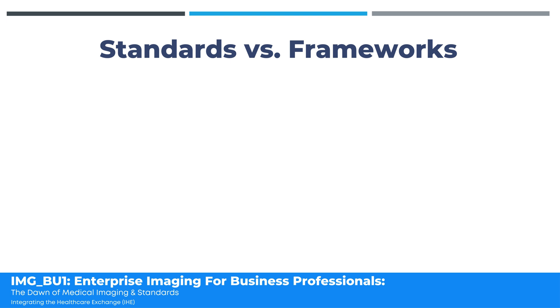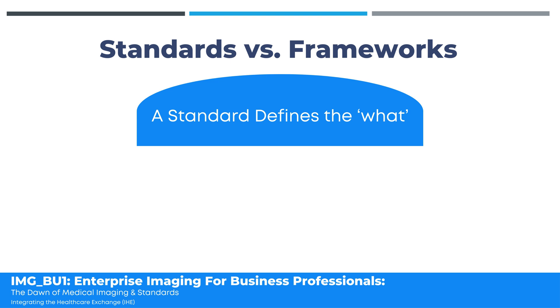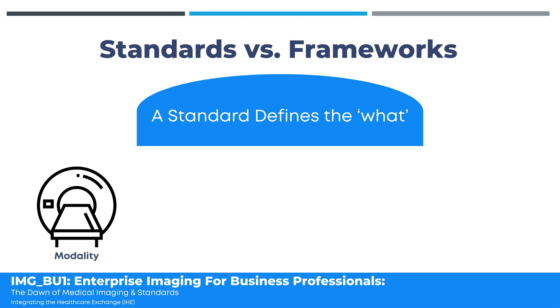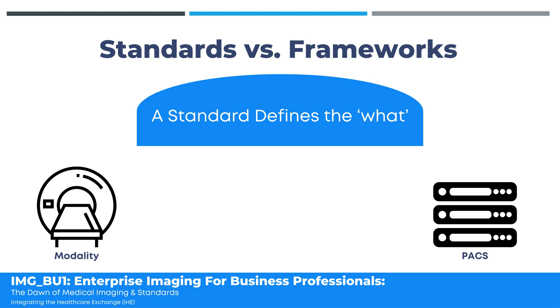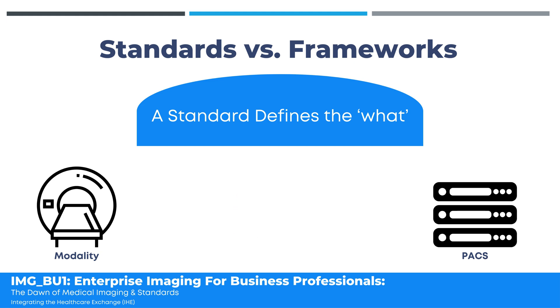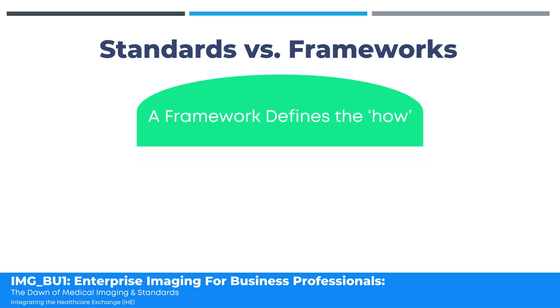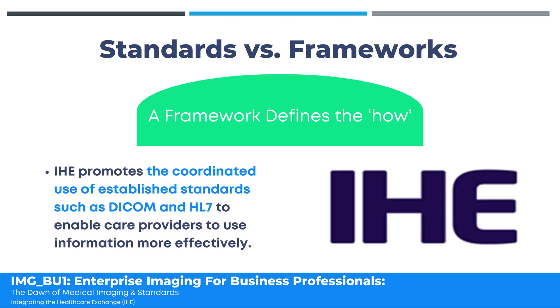The standard allows us to define the what. So we have standards like HL7 and DICOM, and this allows us to have confidence that if I'm using a modality compliant with DICOM and another DICOM node like a PACS, I should be able to send an image from one to the other and have it stored successfully. The framework takes it further — this is where we define the how. IHE comes in as a framework of standards that promotes the use of HL7 and DICOM for the purpose of accomplishing specific clinical workflow challenges.